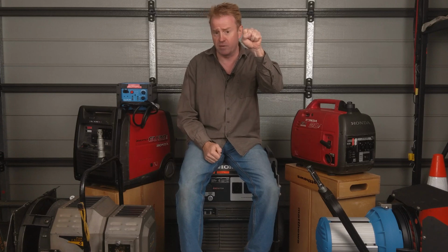Now, the reason for this is the generator that you turn on first is the master. Okay, so imagine that's the generator turned on, that's the master. The second generator you turn on is the slave. So the slave locks into the master. Okay, so they sync up. Now, the master always stays ahead of the slave when you're adjusting your power draws. Okay, so they don't share the load evenly. The master always draws more. So what that means is the master is going to hit its constant load rating or its peak load rating way before the slave. So they're not sharing the load equally.